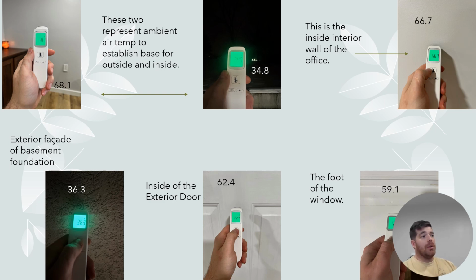All right, so then we go down to the bottom left. We have the exterior facade of the basement foundation, 36.3. Not quite ambient temperature, but not far off. Then we go to a microclimate created by the thermal energy retention ability of a metal door on a metal frame that is braced to the CMU foundation wall. It's 62.4. So it's definitely unable to retain energy on the inside of the door, even though it is heated. So that will create a microclimate there.